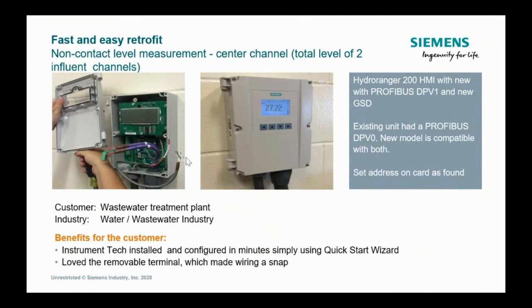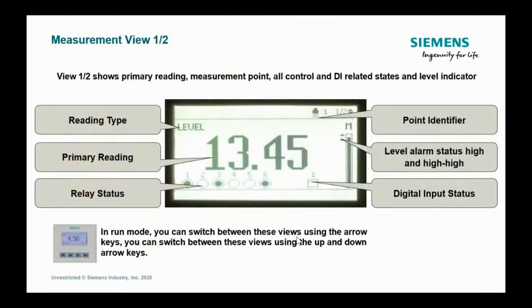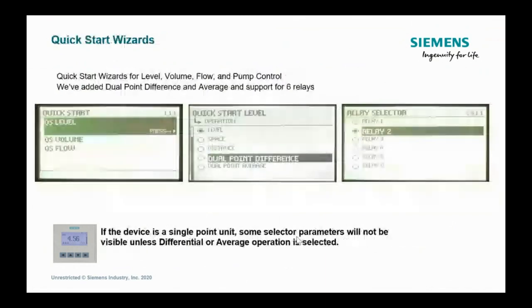One caution with that is that the serial number on the board set no longer matches the serial number on the nameplate on the top of it. But if this thing's been sitting out in the California sunshine for 5 years, guess what? You can't read the label on the outside anyway. So just be aware that you would have a serial number mismatch between the outside and the inside, but it's really super simple to migrate from the old technology to the new. Okay. The display screen isn't a whole lot different than what you had before, showing your level and the status of the relays and whatnot. But what is different is with the 4 buttons and a display, pressing the right-hand button will send you into...